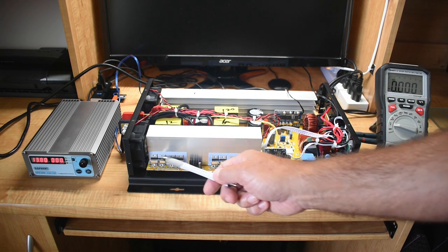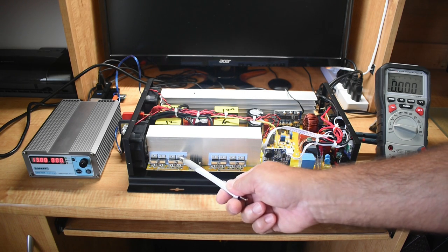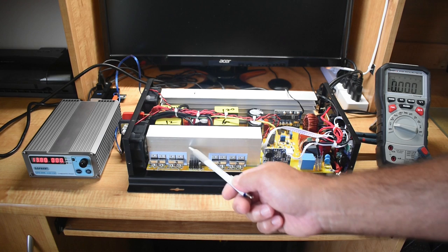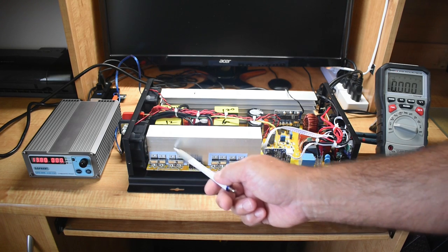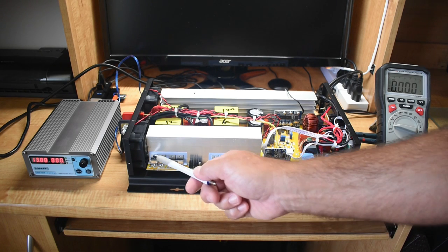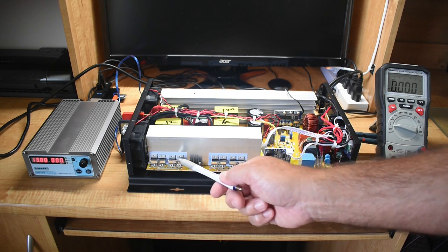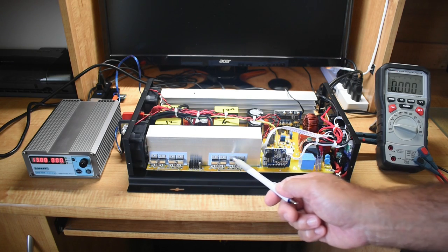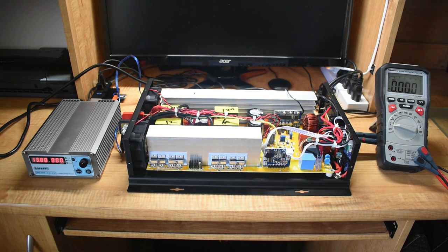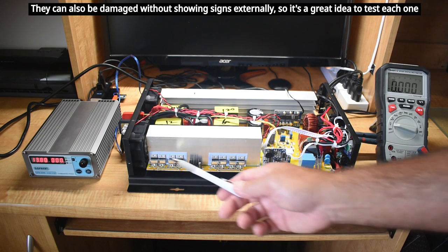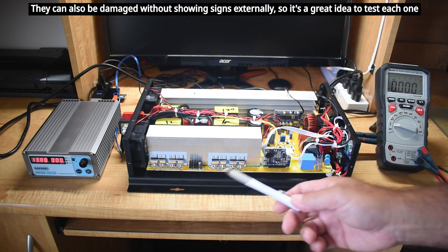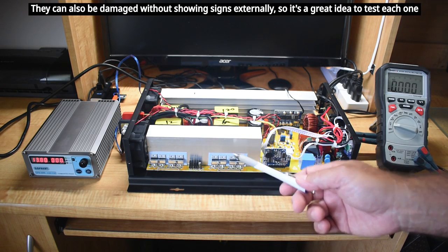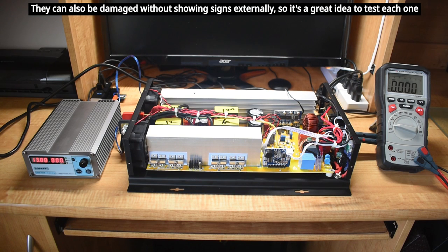When these things blow, they don't go nicely. They usually explode, and you're going to see carbon on the heat sink. So what you want to do is inspect each one of these very carefully. If you don't see anything that looks cracked or burned up, usually they're going to be okay. And that's the case with this unit after it happened during the last test.